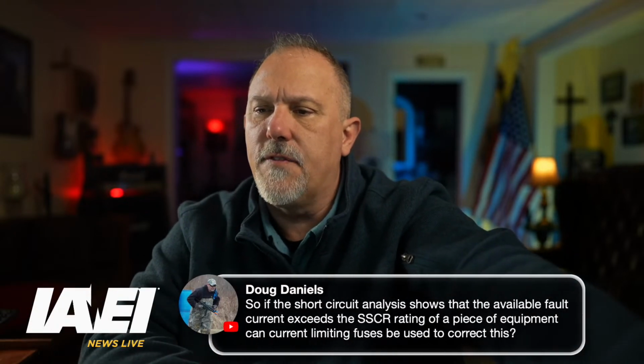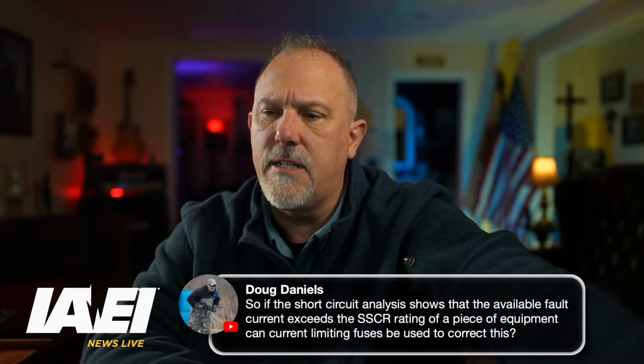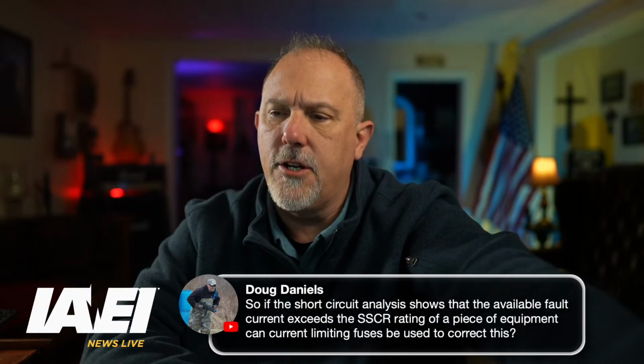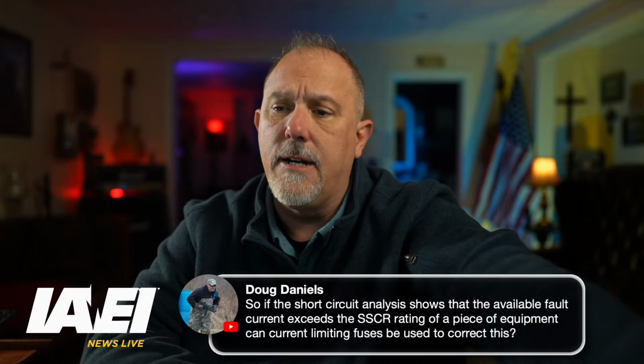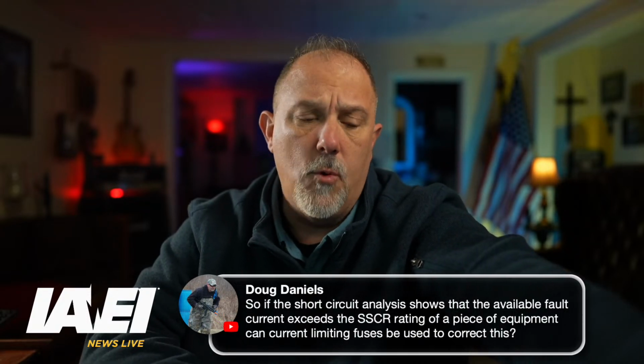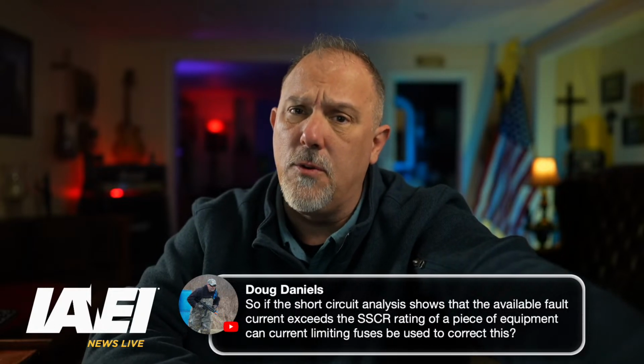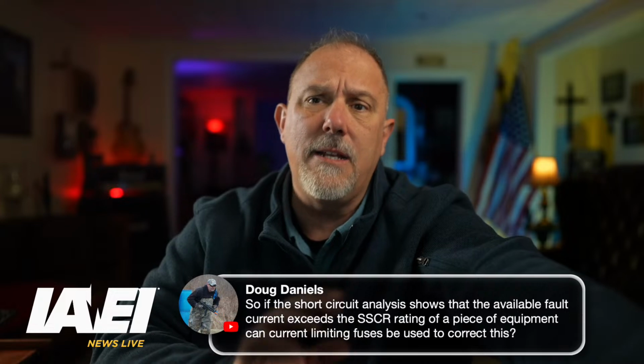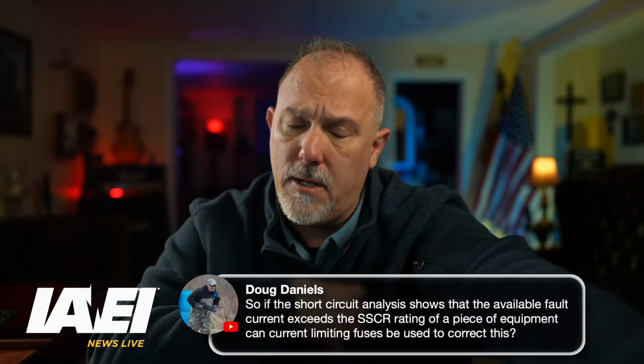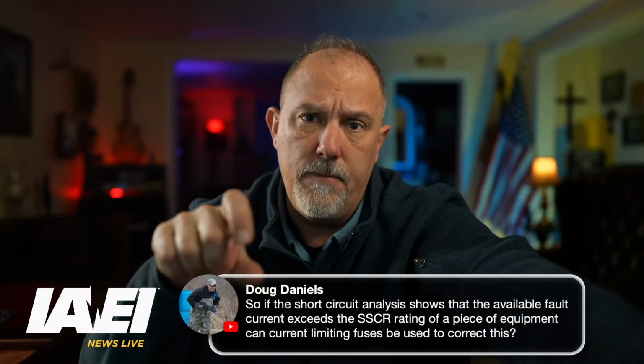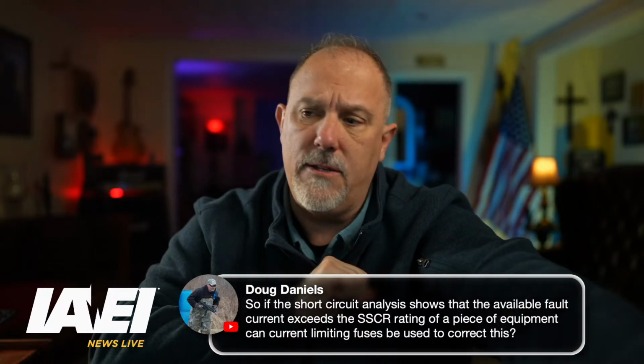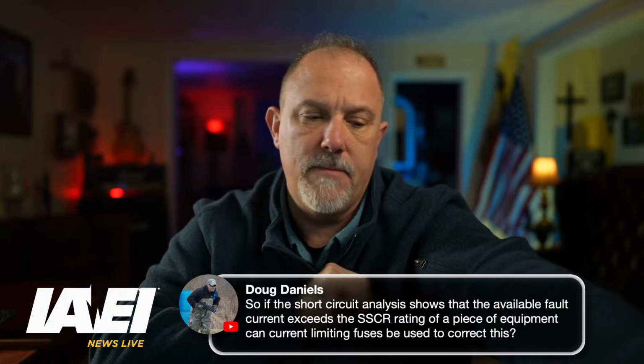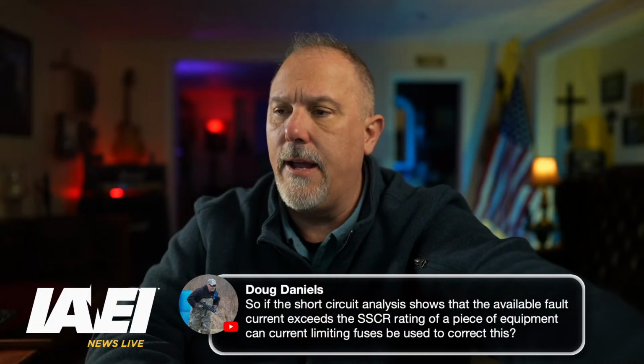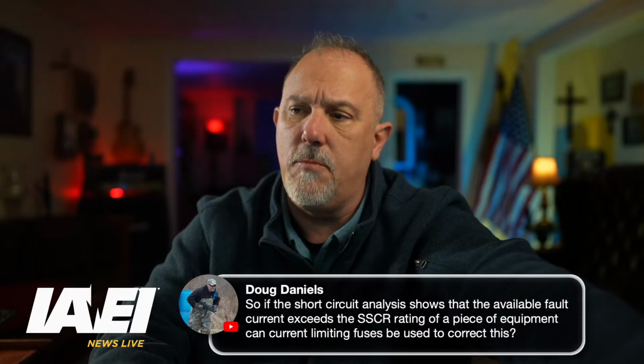Doug says, so if the short circuit analysis shows that the available fault current exceeds the SCCR rating of a piece of equipment, can current limiting fuses be used to correct this? Doug, it's going to be hard to do that. What you can do is limit the amount of energy that you'll let through. You can't increase the short circuit current rating, but in my opinion, you can reduce the hazard, but you're not going to get it to be code compliant. That's just the thoughts on that one. All right, Doug, and if you want to talk more about that, please shoot me a note. I'd love to chat more about that.